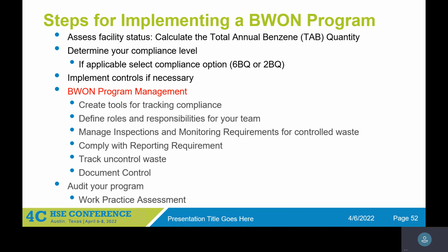Surface impoundments is a visual inspection initially and quarterly, and also Method 21 initially and quarterly. Containers, again, visual inspection initially and quarterly, and annual LDAR, initially and annually thereafter. Closed drain systems have to have the visual inspection initially and quarterly, and the annual NDE. For water seals, this is not here, but you have to do the quarterly visual inspections of the water.